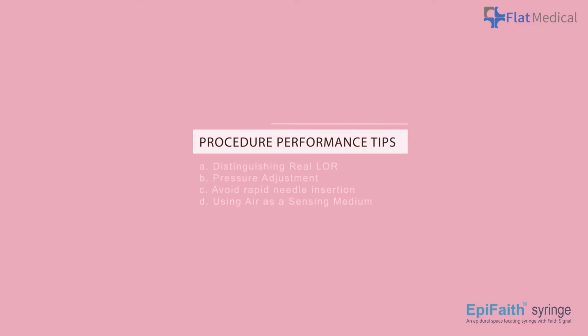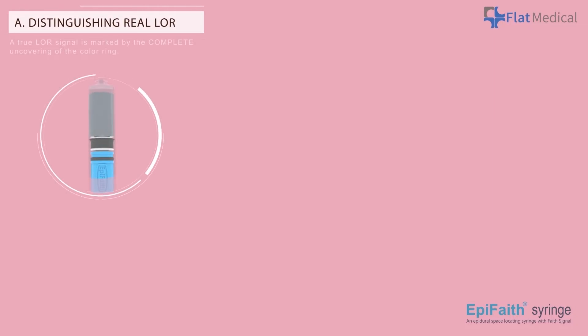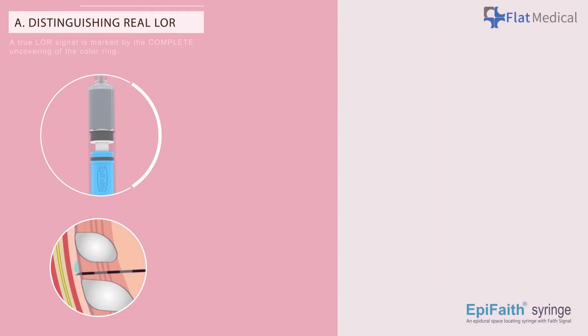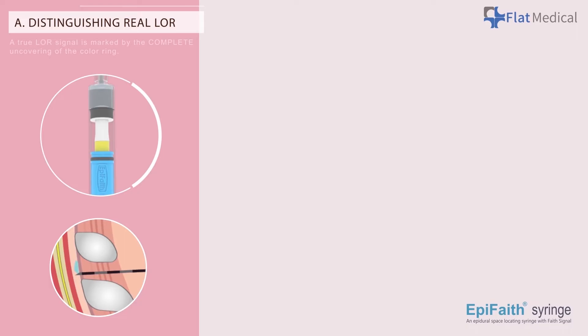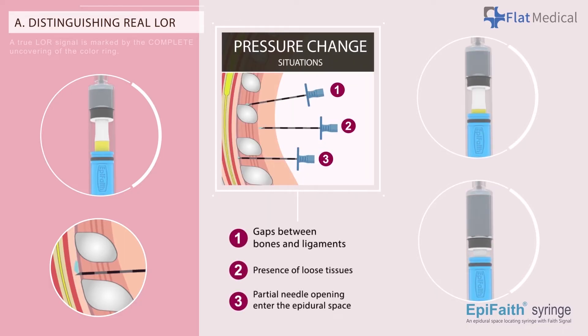Tips to Optimizing Procedure Performance — Distinguishing Real LOR: A true LOR signal is marked by the complete uncovering of the color ring. EpiFaith employs the continuous LOR technique, and factors such as gaps between bones and ligaments, the presence of loose tissues, or partial needle insertion into the epidural space can cause partial movement of the indicator.